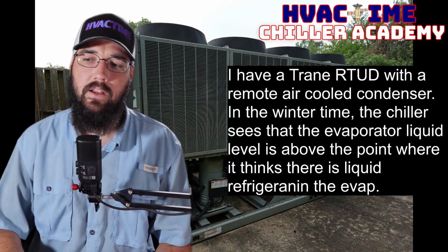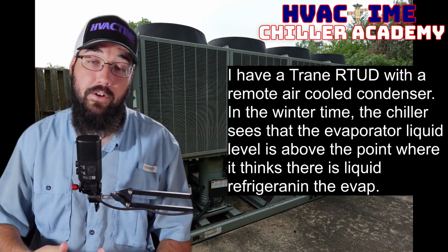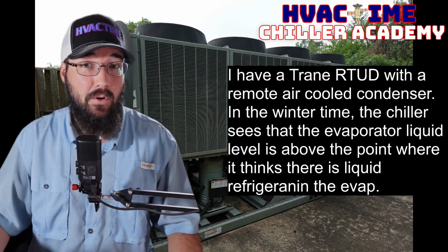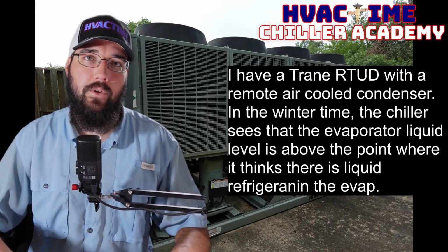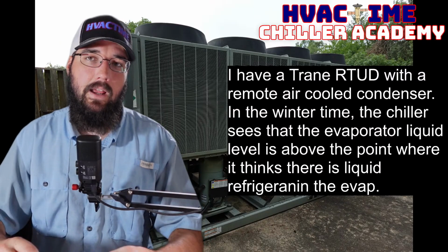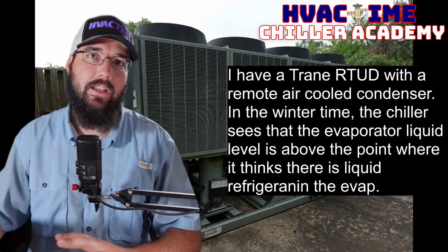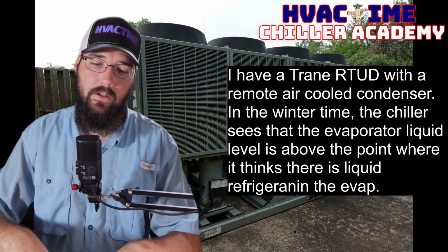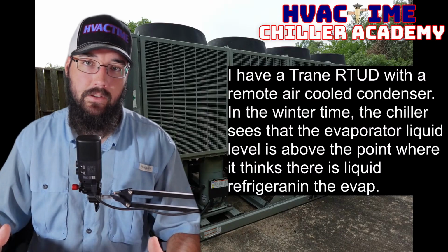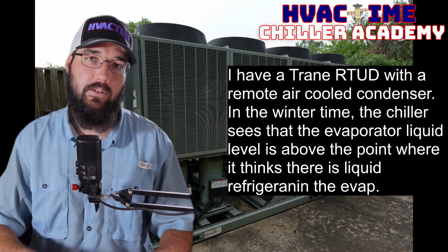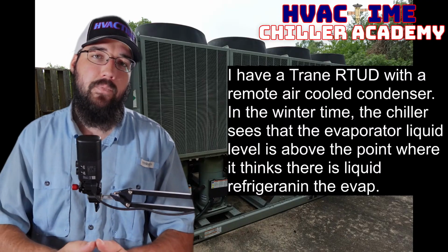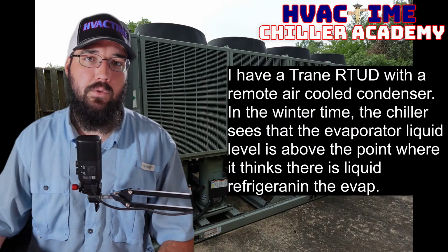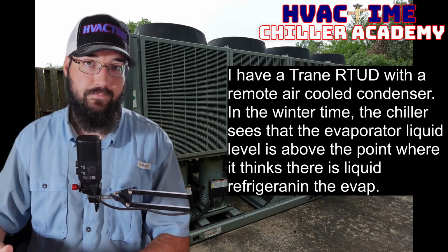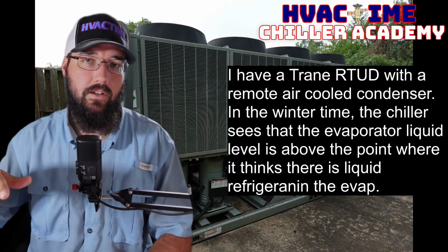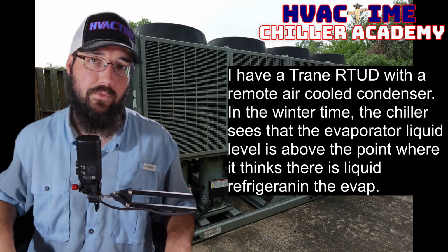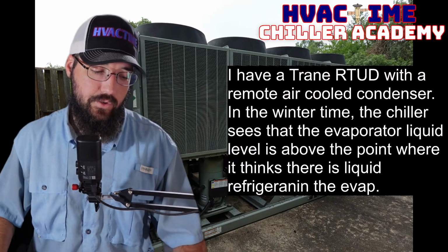You could have a volume of oil stacking in the evaporator, especially as part of operation and as part of pump down. That oil is going to really get disturbed, and in the process of it getting disturbed, it's going to cause a lot of foaming. And especially with the old liquid level sensors Trane was using, they're very susceptible to foam on the evaporator. And that foam will register a refrigerant level higher than the actual liquid refrigerant level is, as one of the issues that those have had.